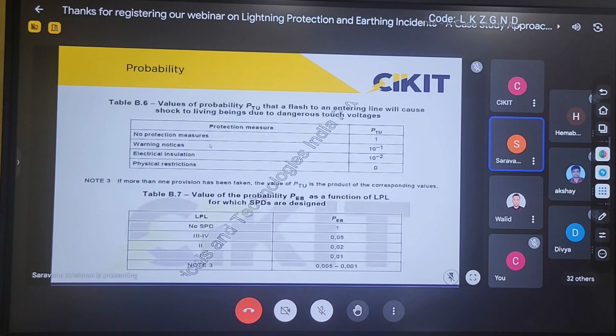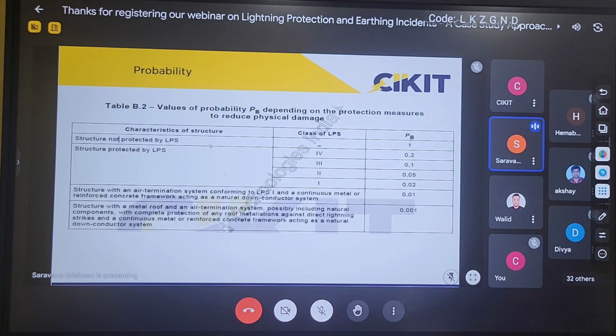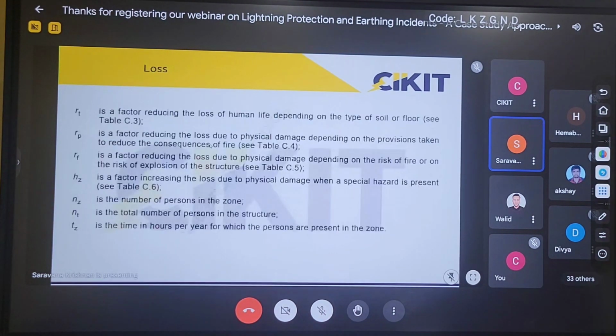So if you observe this, without a lightning protection system, the value of PB will be 1. If I go for level 4, the value will be 0.2. If I am performing the calculation with level 4 protection, I will be substituting the value of 0.2 during the calculation. And if I am working with level 1 protection, I will be substituting 0.02. So this is how, by installing this external lightning protection system, we are reducing the risk due to lightning. I have to repeat this calculation until the value of R becomes lesser than RT.